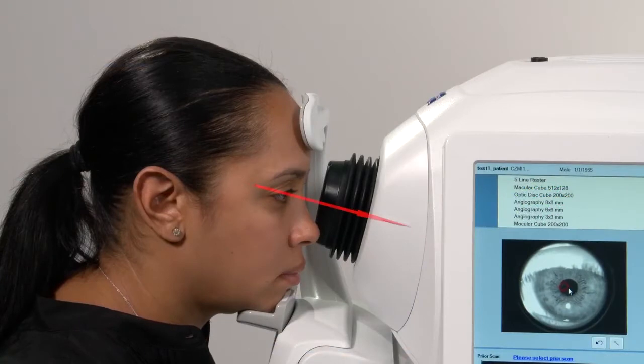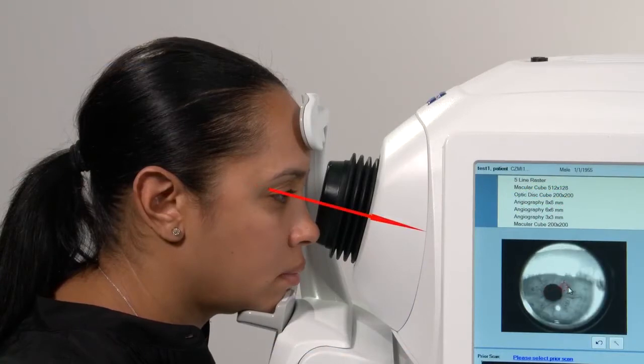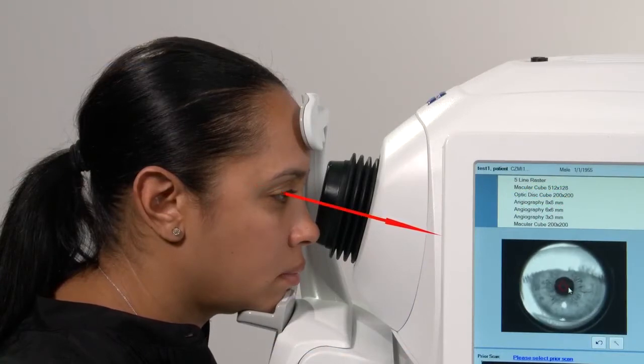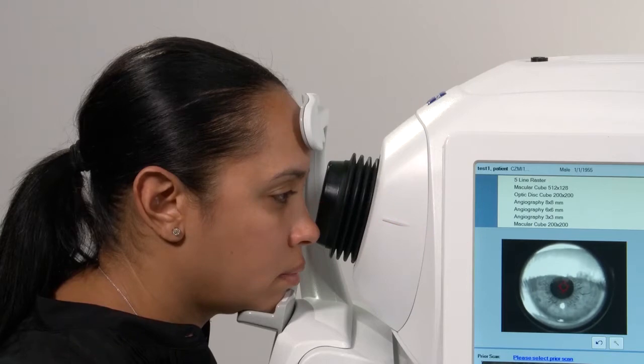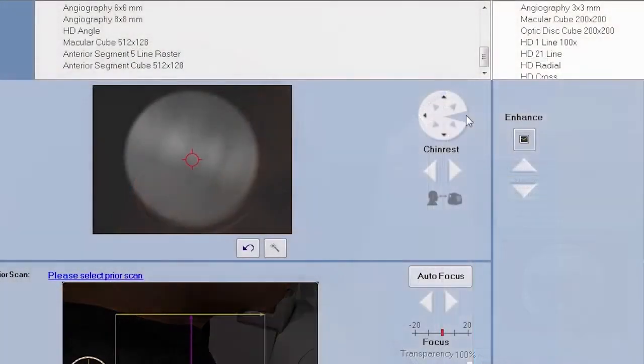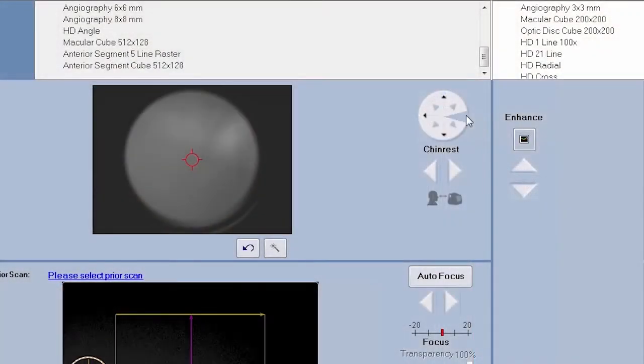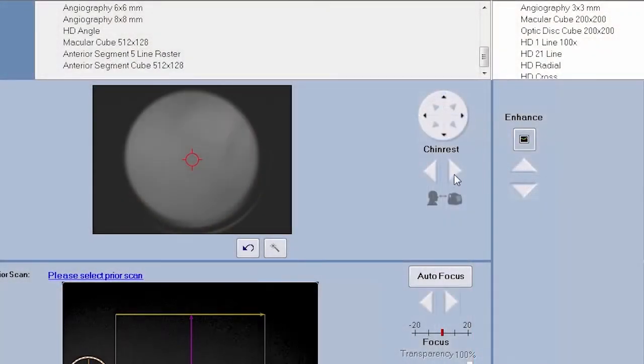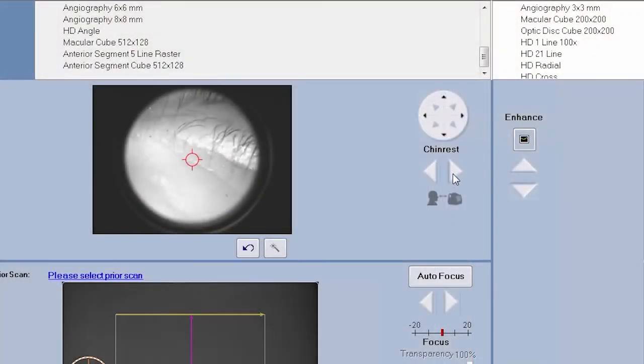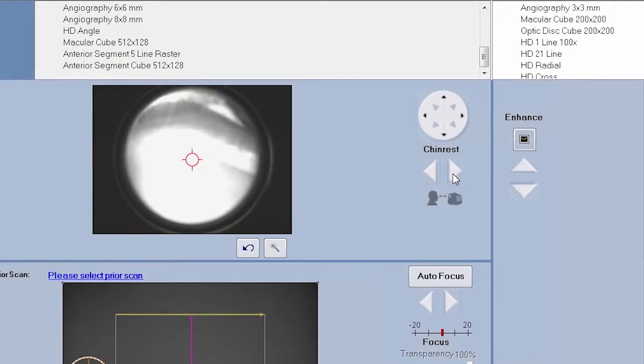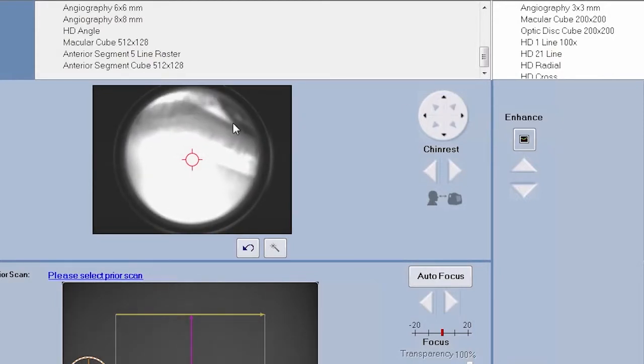Proper alignment of the patient eye to the external marker is crucial to obtaining a good quality scan. Align the patient eye by using the chin rest controls to adjust the position of the iris in the viewport and then align the patient eye with the external marker.